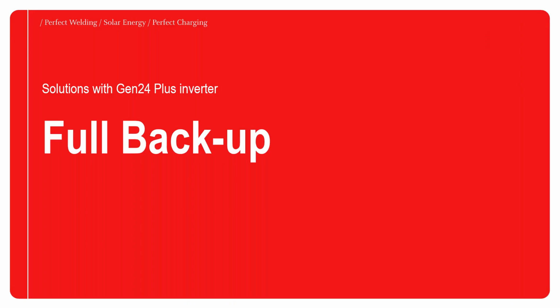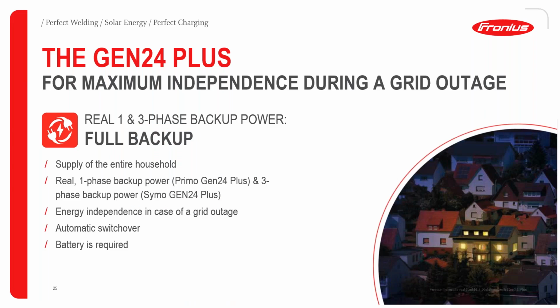Now moving on to full backup. Full backup is only available with the Gen24 series when you have a battery installed. Okay, when you have a single phase Gen24 Plus, you can get single phase backup. If you have a 3-phase Symo Gen24 Plus, you get 3-phase full backup. So when the grid goes down, our Fronius Gen24 will also go down with the grid for about 60 seconds. It will do all its necessary safety checks. It will also send the required signals to the backup box in order to make sure that it's a safe disconnection from the grid, after which it will then come back online and then supply your loads with full backup power.